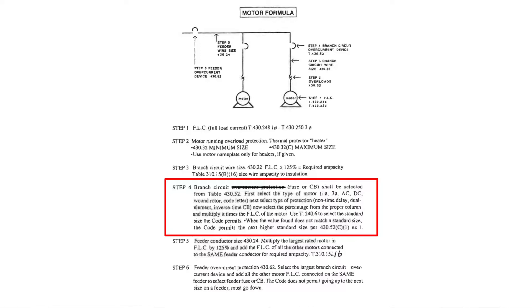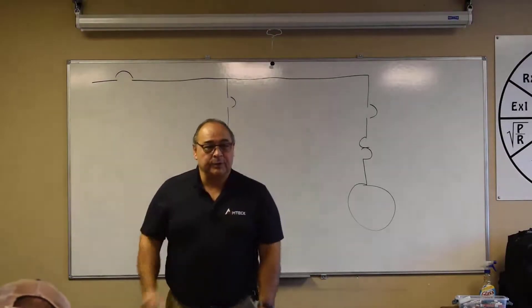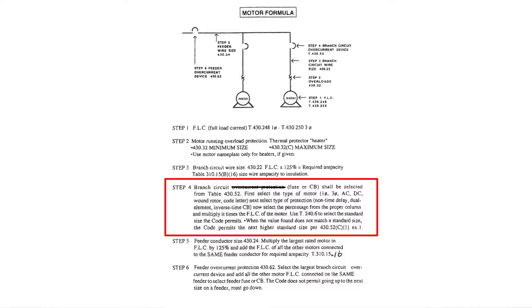So we're talking about a fuse or circuit breaker, yes we are, but we're not using it in the fashion that we normally would. We're using it as ground fault or short circuit protector. It says shall be selected from table 430.52. It says first select the type of motor: single phase, three phase, AC, DC, wound rotor, code letter, all that.